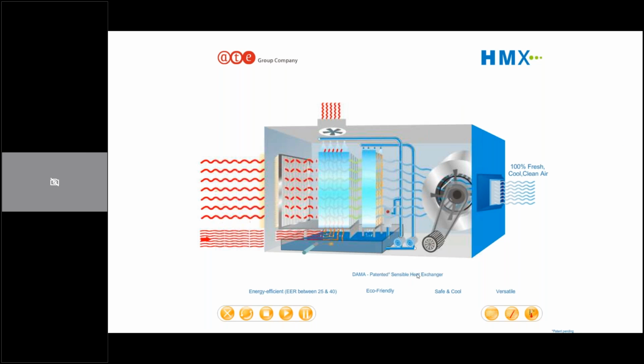Can I ask a small clarification? In the sensible heat cooler also, is there water spraying? Yes, it is, but it is in the exhaust stream, not in the supply stream, the stream which is going into the room. It is in the exhaust stream, which is being sucked through. This air stream comes from below, goes through the alternate passage, not the passage in which the supply stream is moving, and is discharged out.